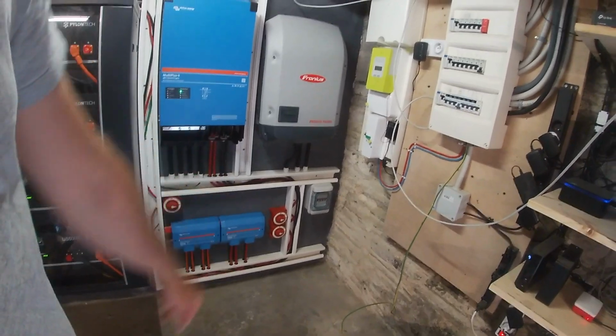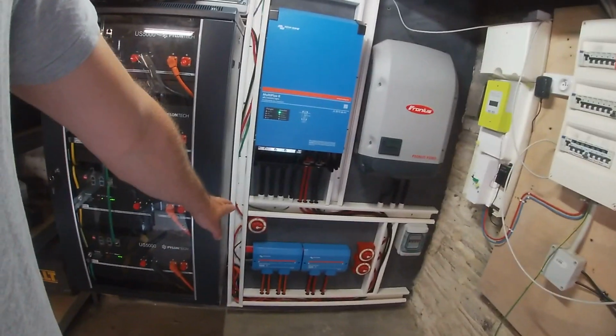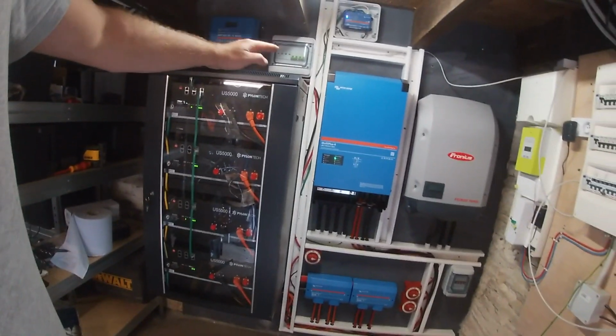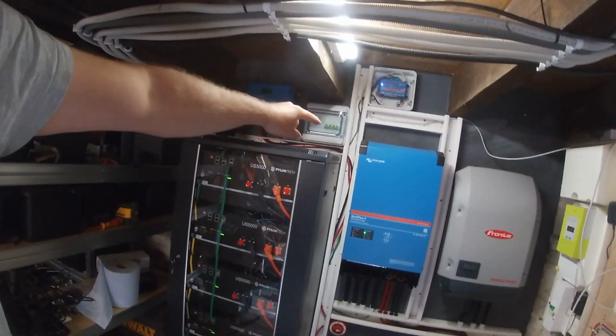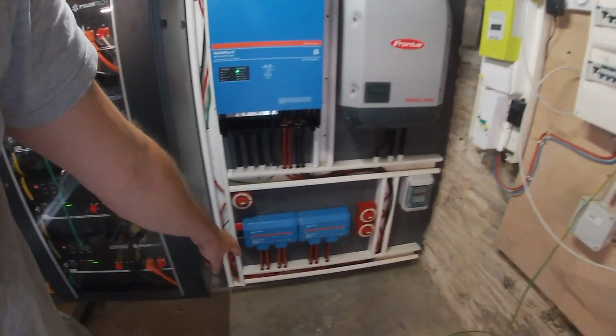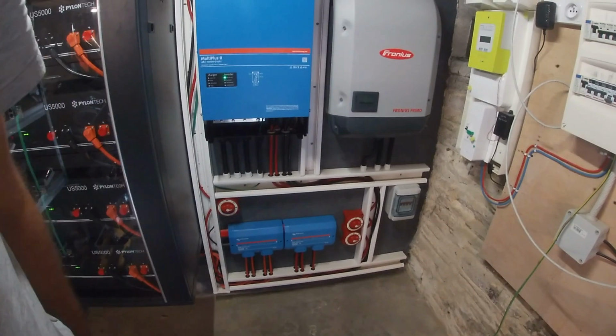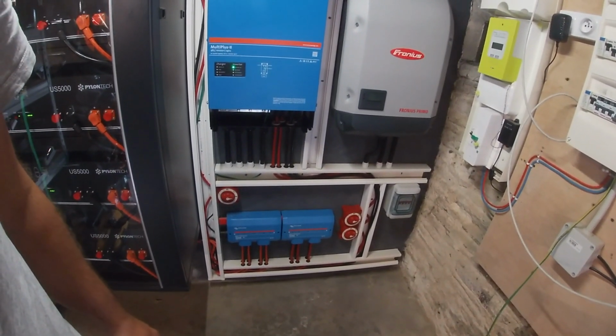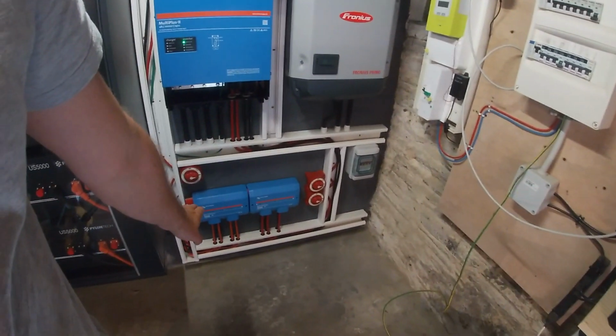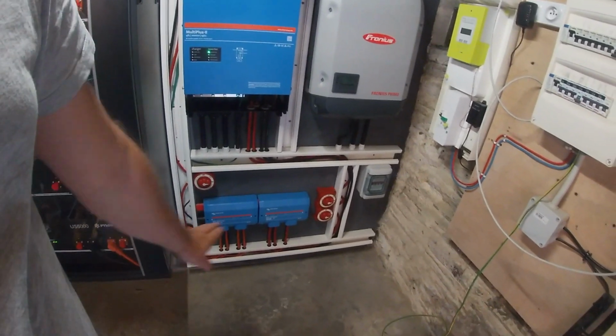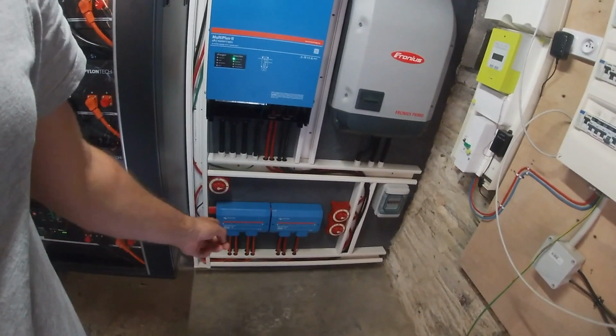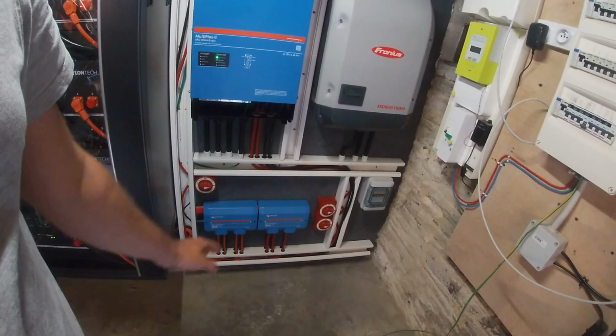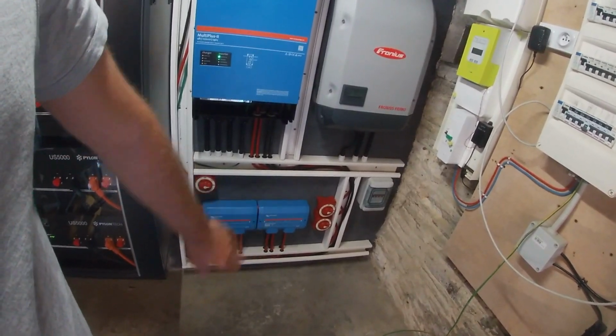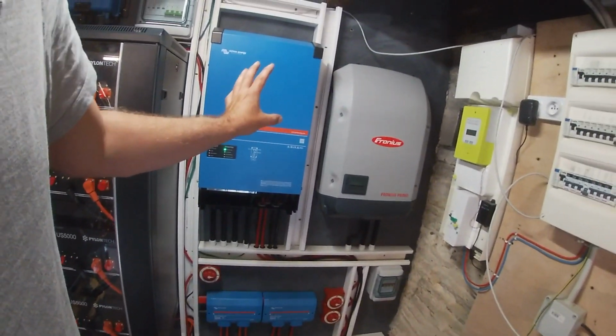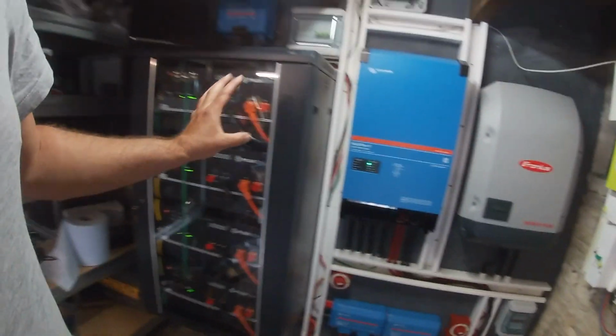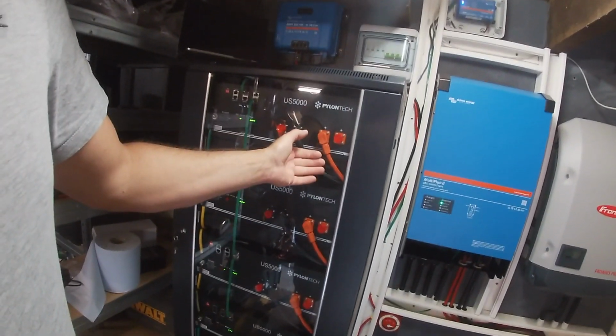You've already seen those two on-off switches for the multi-plus, and the on-off switch for the solar charger. The cable comes down into there and then up into the battery bus bar. Inside the distributor it's just metal bars where you can put fuses in, so they're all fused, and it connects your appliances and inverters to your batteries using really thick cables.